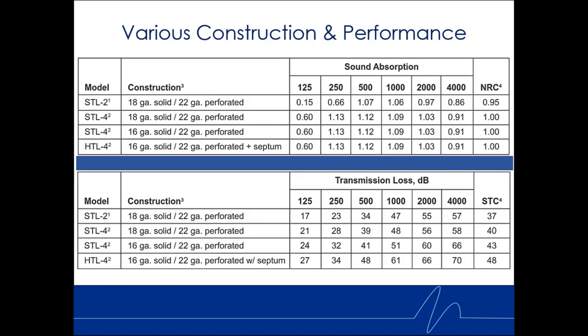When you look at various constructions and performance, we do publish data, whether you're looking at sound absorption, which is the top chart here, with different thicknesses like the 2 and the 4 inch, and different models. This one has an 18 gauge solid, 22 gauge perforated inner shell. We have a 16 solid, 22 inner shell. This is a 2 inch thick, this is a 4 inch thick. And the last one actually has a perforated inner shell and solid outer shell, then an additional solid septum at the midpoint of the 4 inch thickness. That gives you even more noise control. But the key here is that we publish data for you to use.